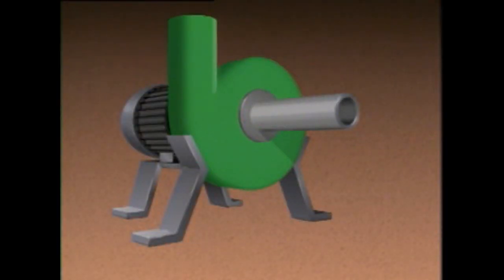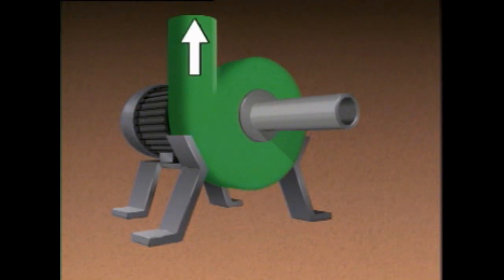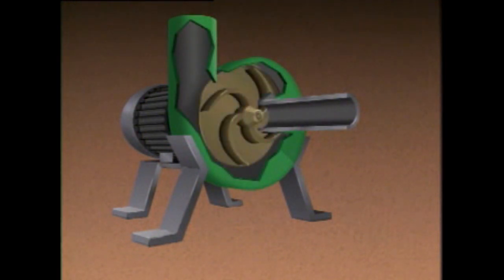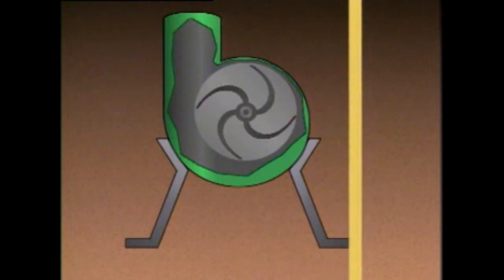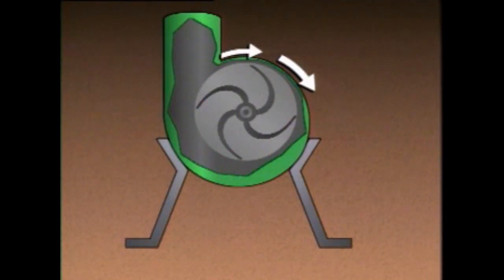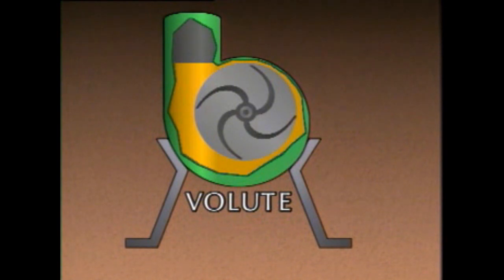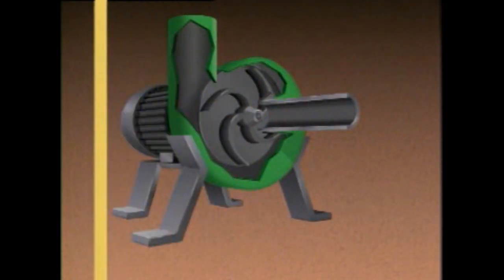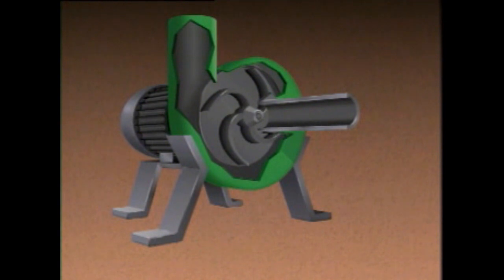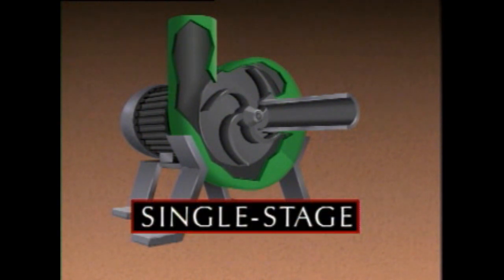We can see how a centrifugal pump works by using this simplified illustration. All centrifugal pumps have an inlet, a casing, and an outlet. Inside the pump's casing is an impeller with a series of curved vanes that extend out from its center. The pump's casing is designed so that the area around the impeller creates a gradually widening spiral channel known as the volute. Since this pump has only one impeller and one volute, it is referred to as a single-stage pump.